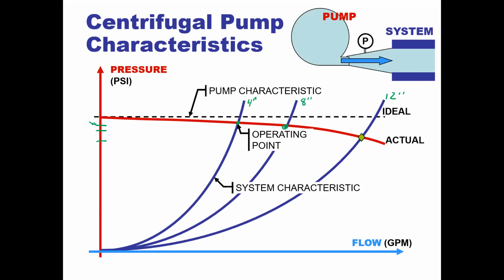So if it's not so much of a specific pressure that you're after, what you're caring about is your flow - that's how you can change and manipulate it, through your system characteristic. So what if we go way back? We see at an 8-inch, again follow the 2 lines. We go back even more, we go to that 4-inch pipe, it's more restrictive, less flow. And even less, we go to a 2-inch piece of pipe.